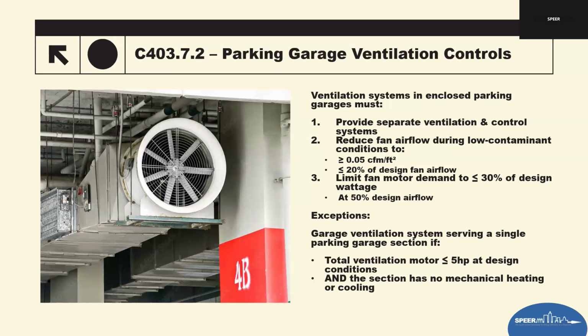2, fan airflow must reduce when contaminations are low. So parking garage ventilations must be able to automatically reduce fan speed down to a minimum of 0.05 CFM per square foot and no more than 20% of the design airflow. This essentially ensures turn down capability for low use or low contaminant periods. Fan power requirements: at 50% airflow, the fan motor cannot use more than 30% of its design wattage.